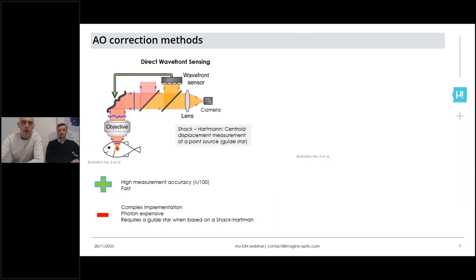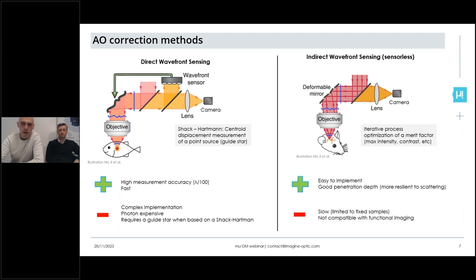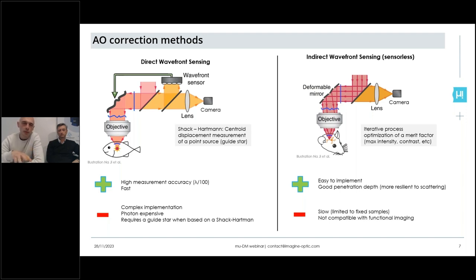There are two main ways to correct optical aberration in microscopy. The first is a direct wavefront sensing method that makes use of both a wavefront sensor — typically a Shack-Hartmann wavefront sensor — and a wavefront modulator, typically a deformable mirror. The wavefront sensor directly measures the aberrations and transforms this measurement into a set of commands to the wavefront modulator, running in a continuous feedback closed-loop system.